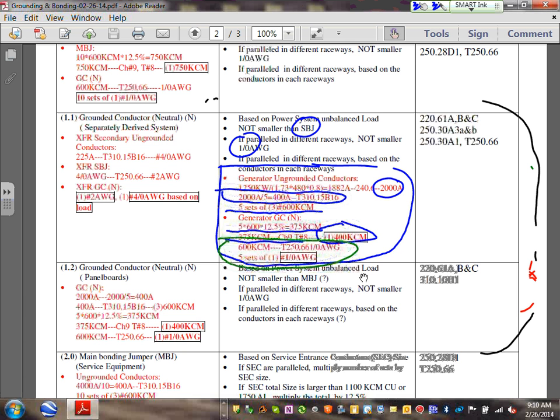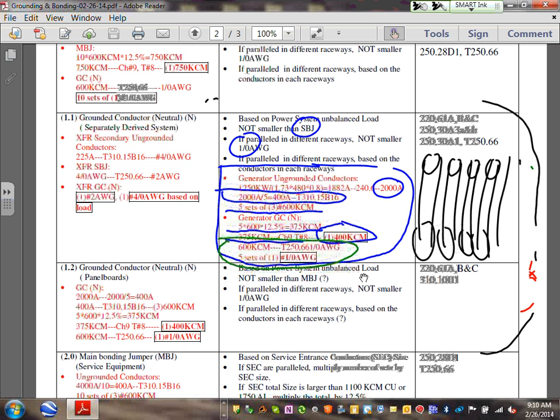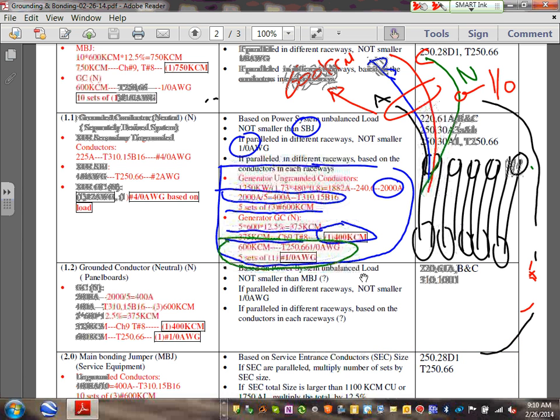So your conduit here, here's my conduit 1, conduit 2, conduit 3, 4, 5, and I'm going to show you only one conduit of them, and a conductor coming to me. Here's phase A, and here's my phase B, and let's do phase C coming with it. Here's my phase C, and I'm going to take my neutral, and here's my neutral conductor. These three will be 600 kcmil, and my neutral will be 1/0. Can you guys see that? That's what I sized, and each one of these conduits will be carrying the same thing. I don't want to sit there and draw it. Can you imagine that each one of these 5 conduits will be carrying 4 conductors each? Three of them are 600 kcmil, and the neutral will be 1/0. You have just sized a neutral for the generator.